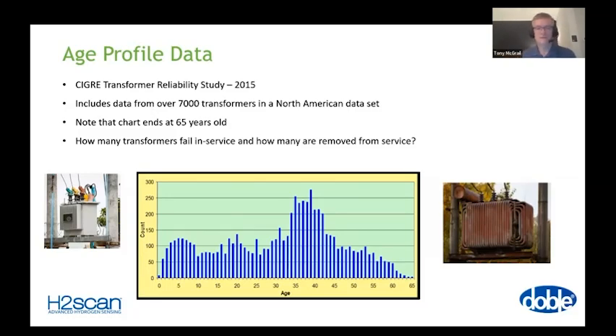Things, as far as I know, don't fail just because of their age. They fail because there are failure modes which exhibit themselves over time, and that time is the age of the unit. For example, the number of through faults we see on a transformer will increase not because the transformer is old, but because it's old and in a particular area. The degradation of paper, which is a one-way process, results from temperature, oxygen, and moisture. Those three things act upon the paper over time. So time by itself needs something to make the transformer deteriorate, and we call it aging, even though age itself is not an indicator of whether the transformer is in good or bad condition.